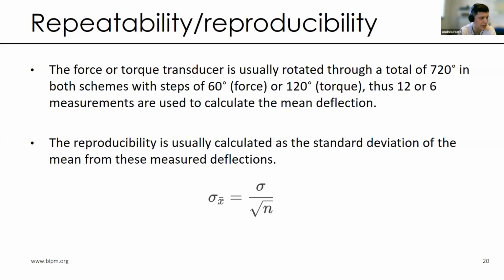So the idea is to perform different measurements, and usually these transfer standards are rotated through a total of 720 degrees with different steps, usually steps of 60 degrees for force transducers and 120 degrees for torque transducers. In this case, we get a total of 12 measurements for force transducers and 6 measurements for torque transducers. As mentioned, we calculate reproducibility as the standard deviation of the mean. The more measurements are performed, the lower the uncertainty related to the reproducibility. So this is why we perform so many rotations compared to typical standards like ISO 376.